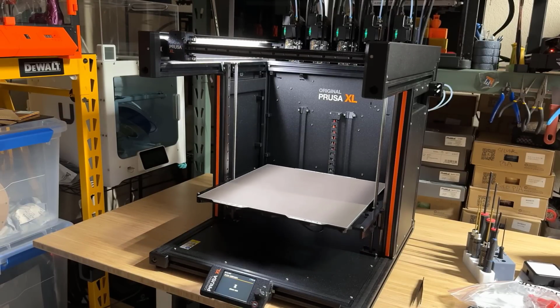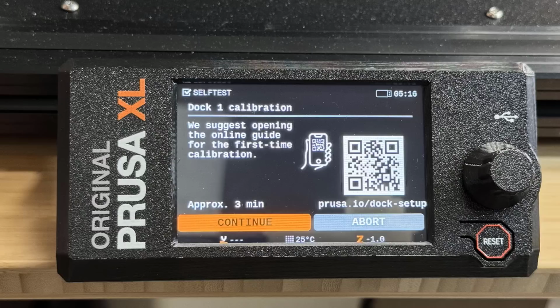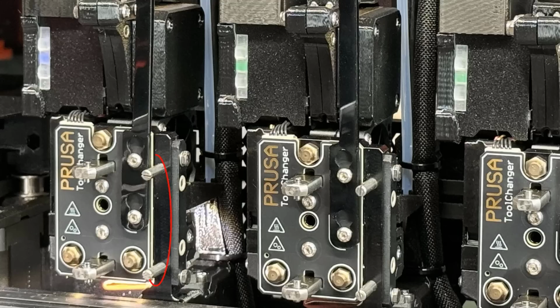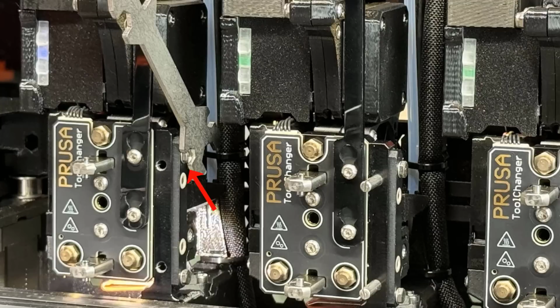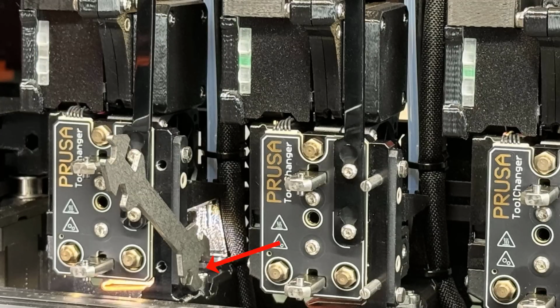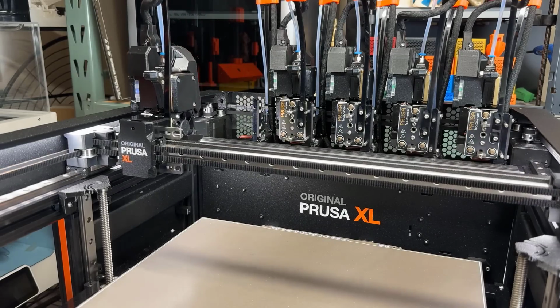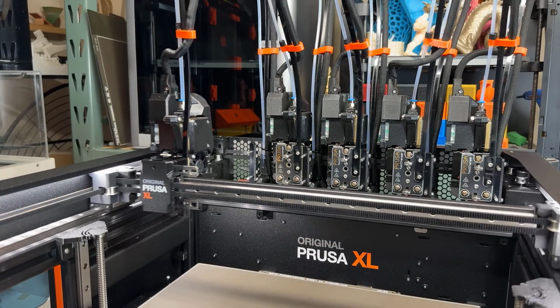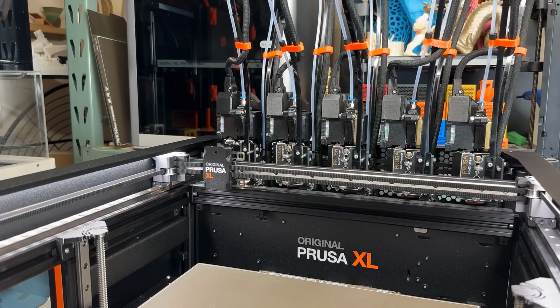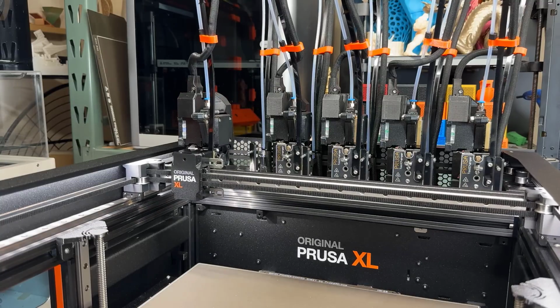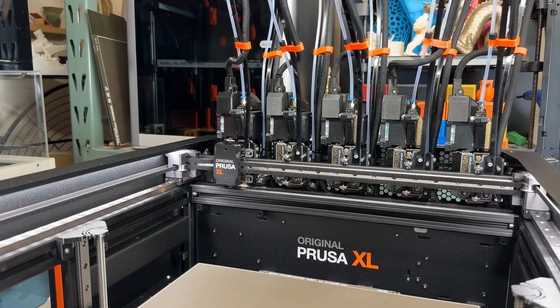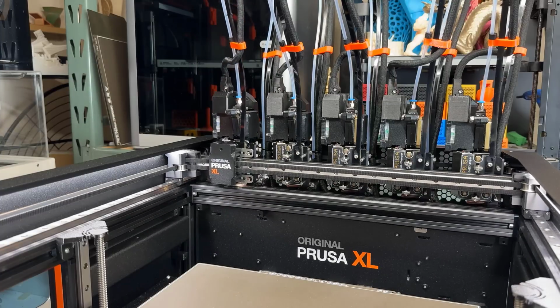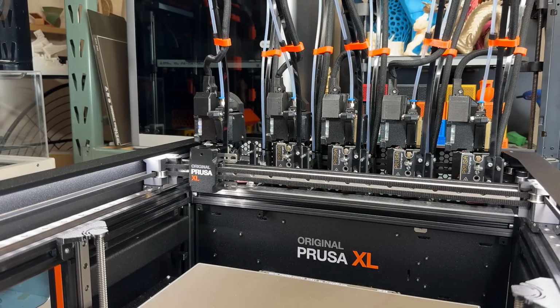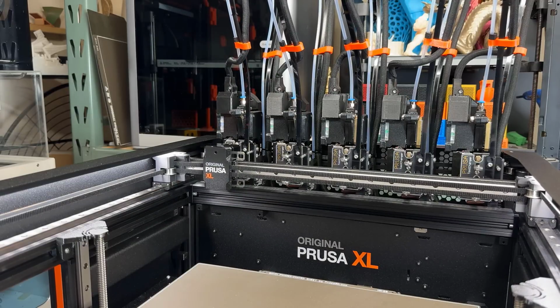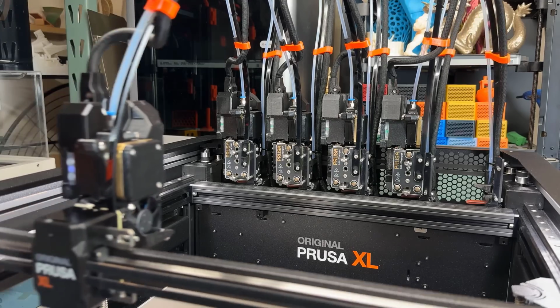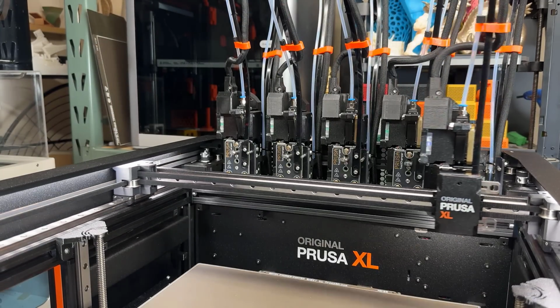The first task requiring careful attention is calibrating the tool head position. This involves unscrewing 2 pins and loosening 2 nuts following the on-screen instructions. The machine will then pick and park the tool head a few times. There should be no wiggling, and your tool head should mount solidly. Repeat this process for each tool head, which takes about 20 minutes for 5 tool heads.